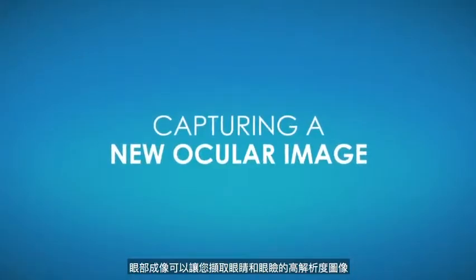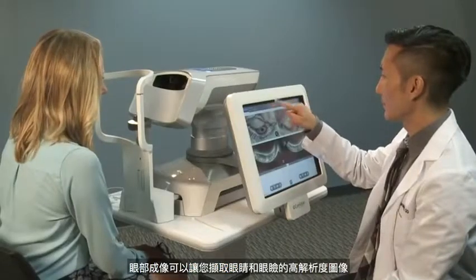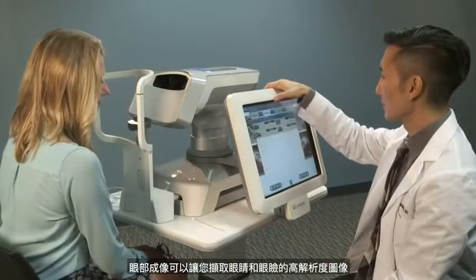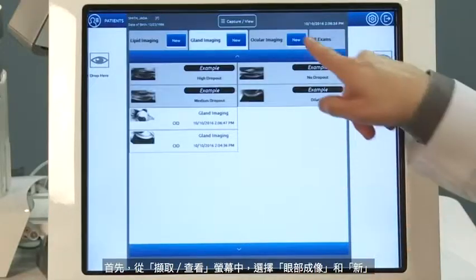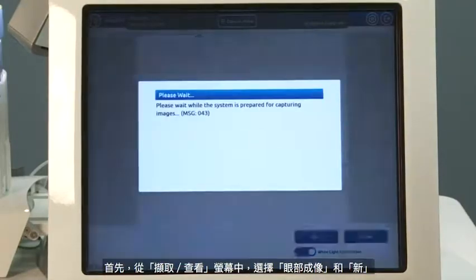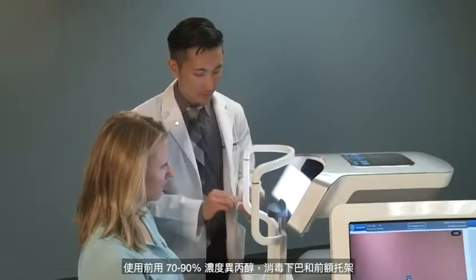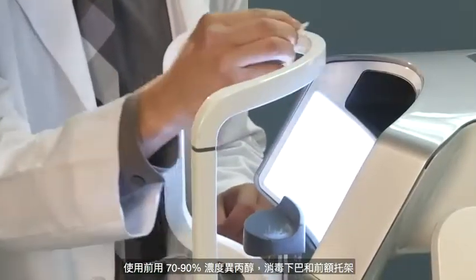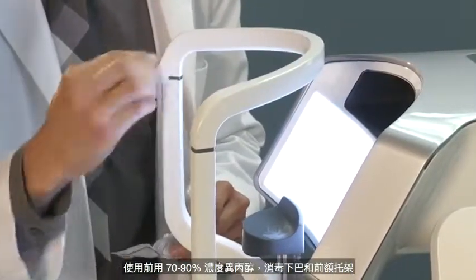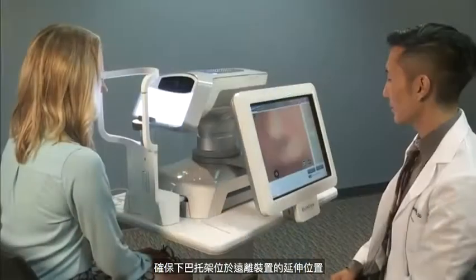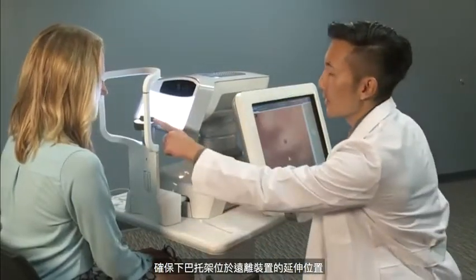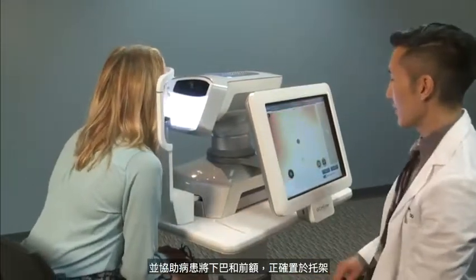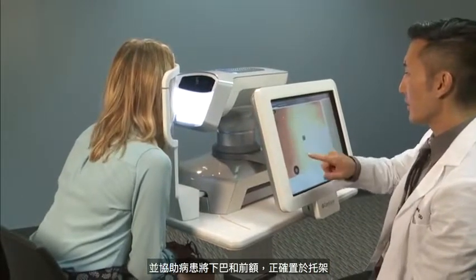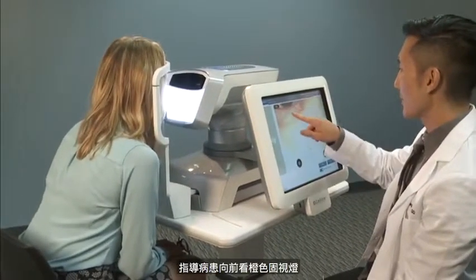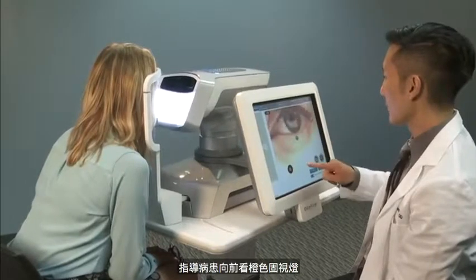Ocular imaging allows you to capture high-resolution images of the eye and the eyelids. To begin, select Ocular Imaging and New from the Capture View screen. Disinfect the chin and forehead rest with 70 to 90% isopropyl alcohol prior to use. Make sure the chin rest is in the extended position away from the device and position the patient properly into the chin and forehead rest. Instruct the patient to look forward at the orange fixation light.